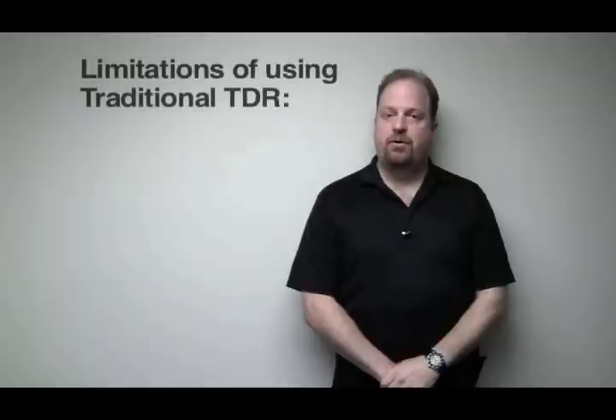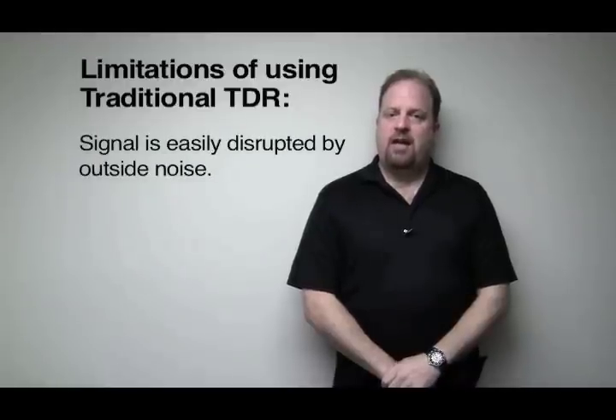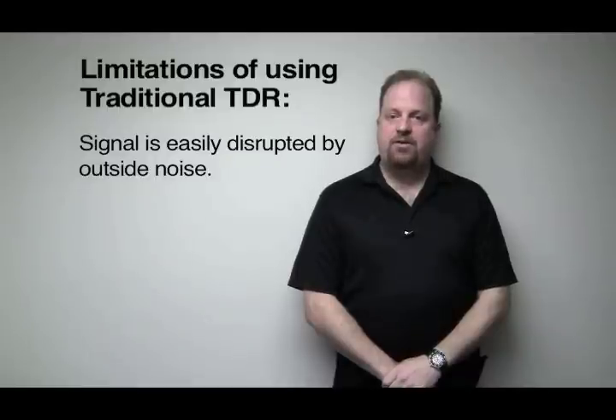Although TDR was a groundbreaking technology, it has limitations. First, the signal you send down the wire is a single pulse of energy. The problem with this is that any and all electrical noise can and will corrupt the TDR signal as it travels along the wire.